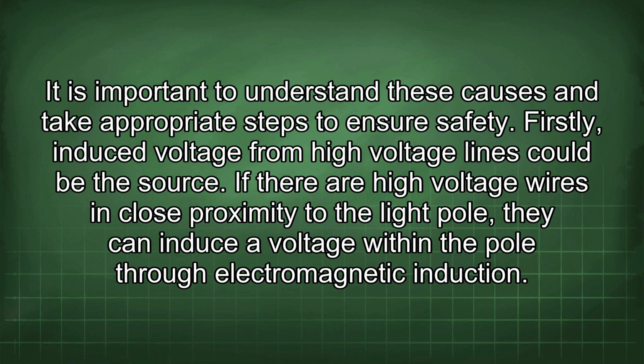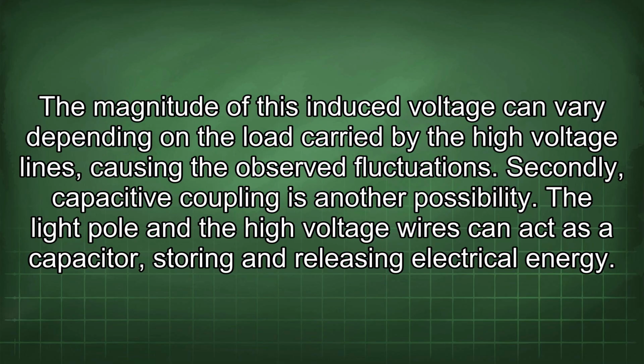Firstly, induced voltage from high voltage lines could be the source. If there are high voltage wires in close proximity to the light pole, they can induce a voltage within the pole through electromagnetic induction. The magnitude of this induced voltage can vary depending on the load carried by the high voltage lines, causing the observed fluctuations.